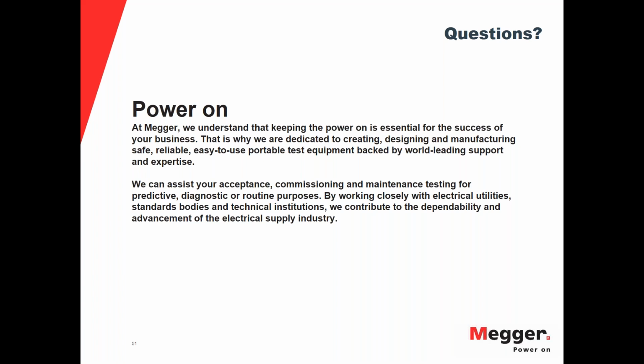All right, what is your opinion of conductance testing versus capacity testing? So when we talk about conductance testing in the standards or the guides, the term ohmic testing is used, and there are different ways of doing ohmic testing. What we promote is impedance testing, though there's also conductance testing or resistance testing done. So if I had to talk about impedance testing versus capacity testing, both look at two different things. Impedance testing is a check of the electrical path in the system. So what you do is you measure the impedance of the cells, you measure the resistance of the straps connecting those cells, you measure the DC voltage.